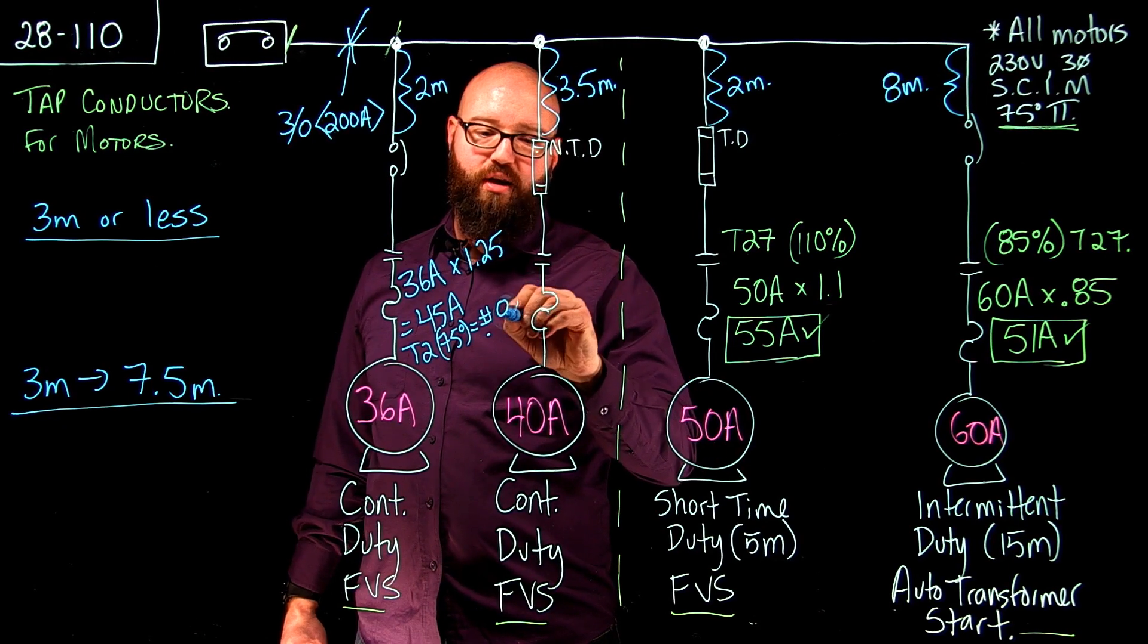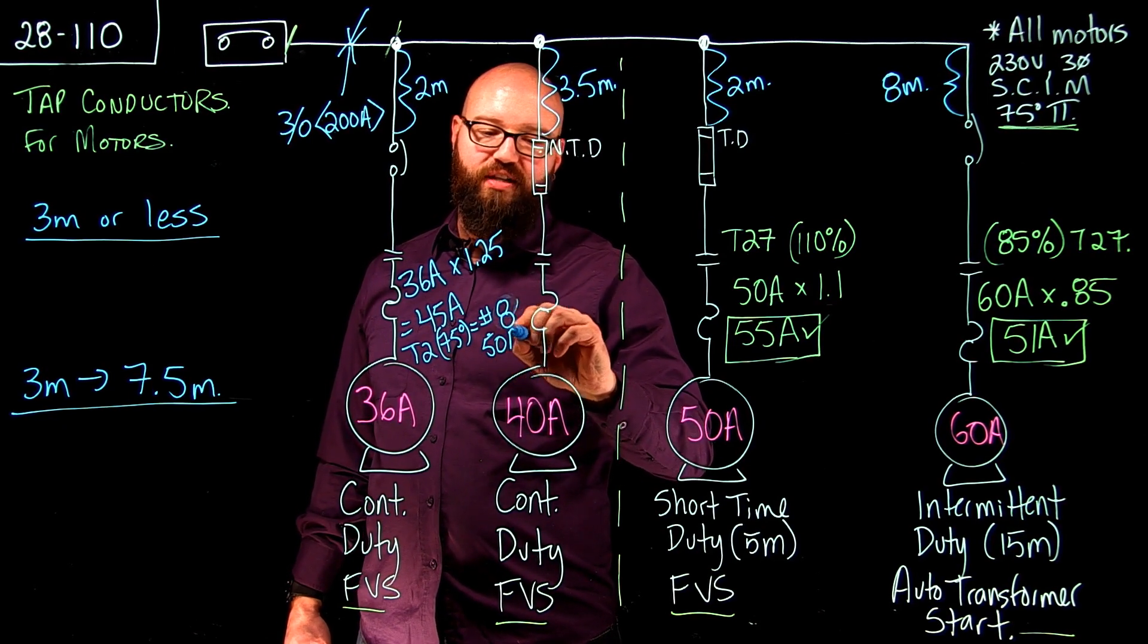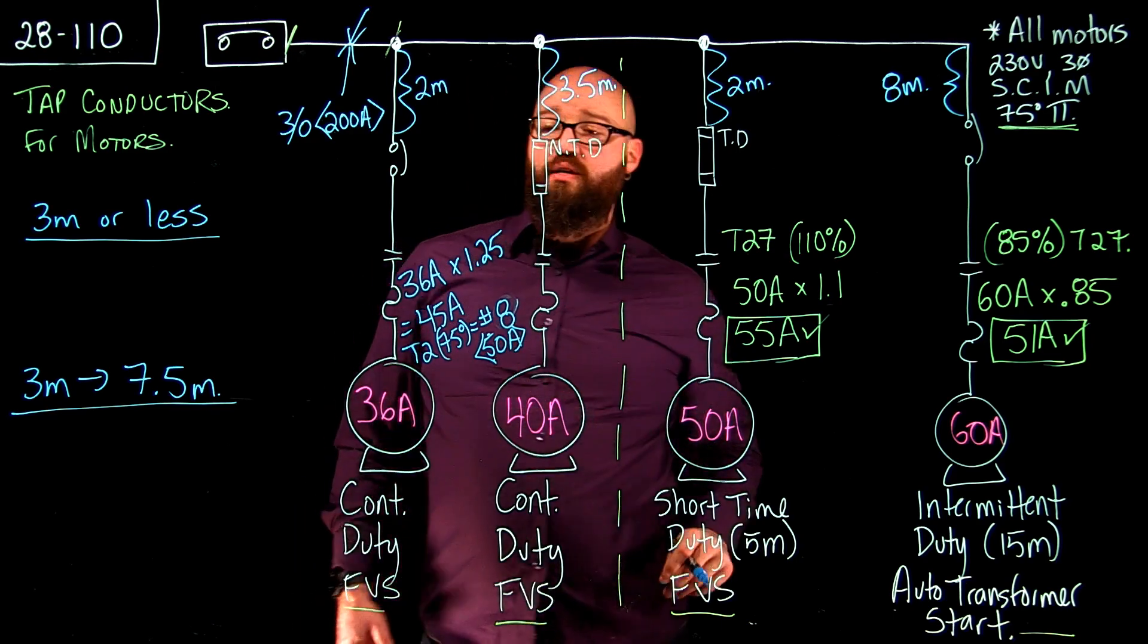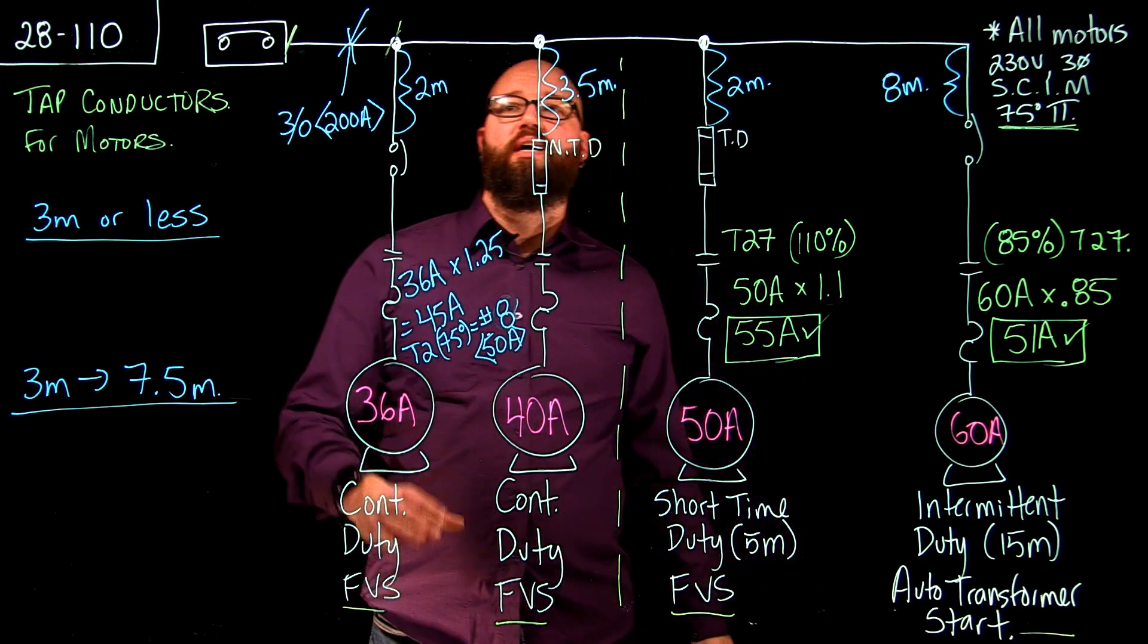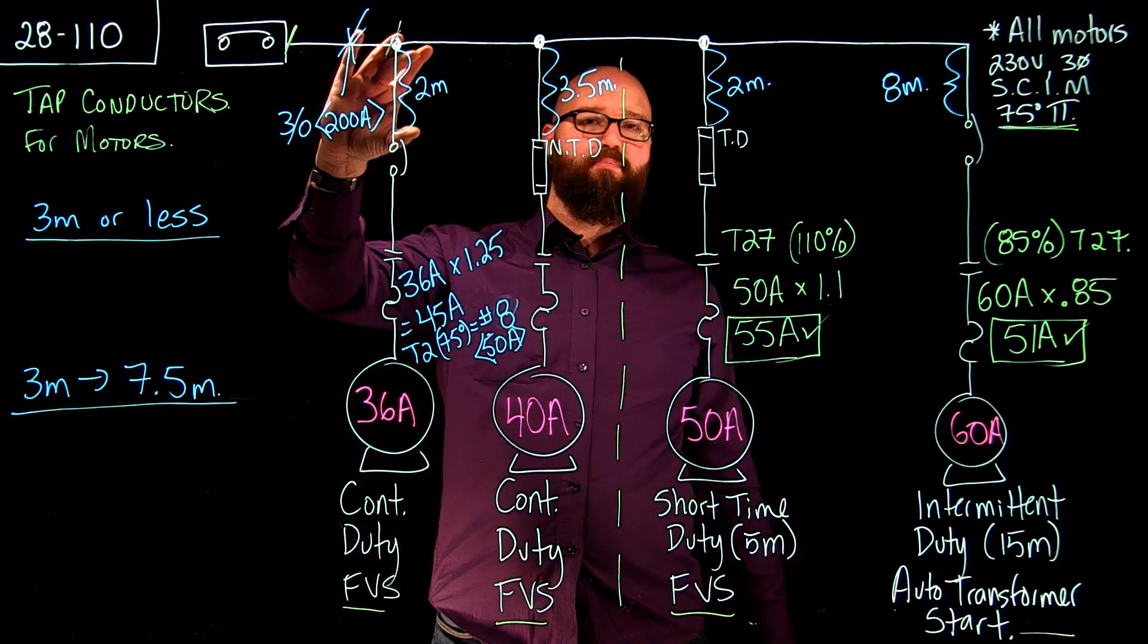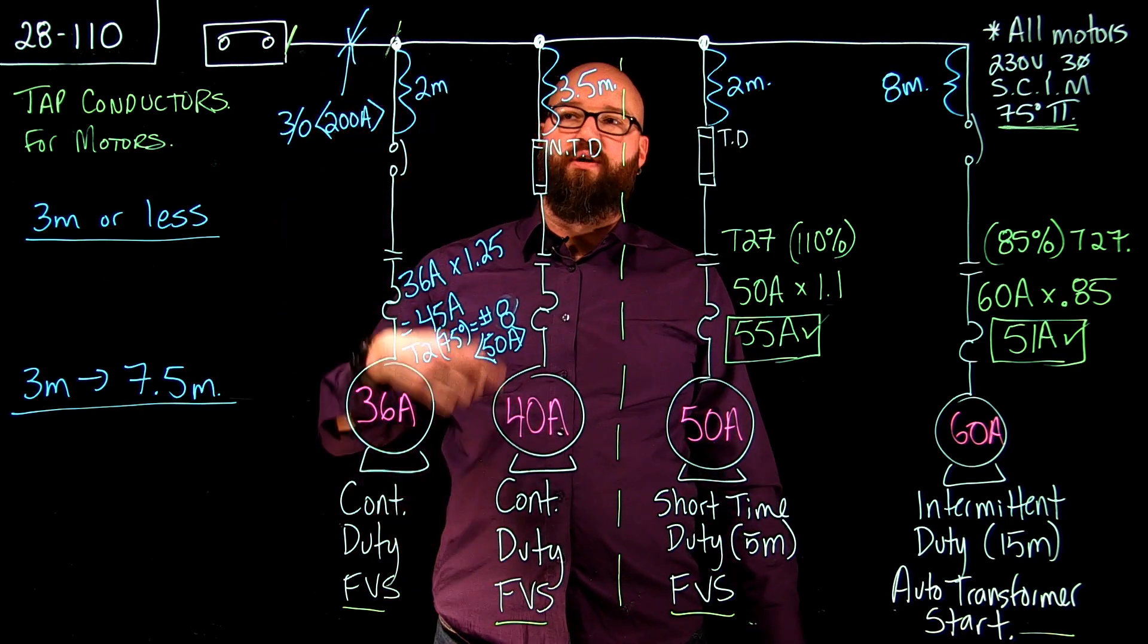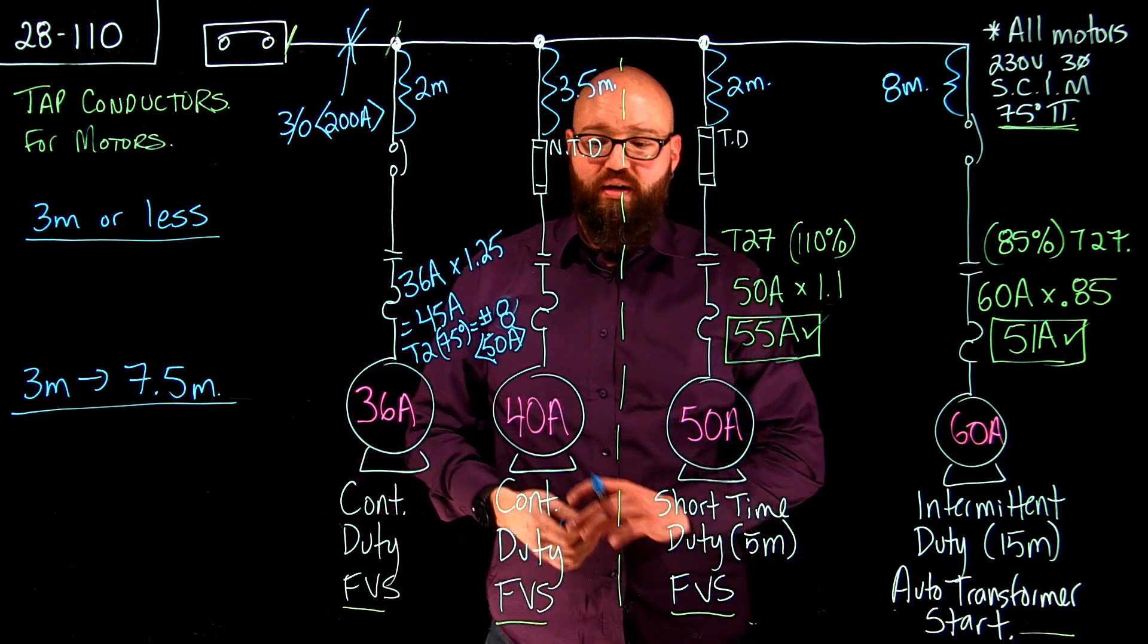We're going to go with a number 8 gauge that's good for 50 amps. So that's my branch circuit conductor and because I'm less than 2 meters on my tap I can also use a number 8 gauge for a tap conductor here as well.